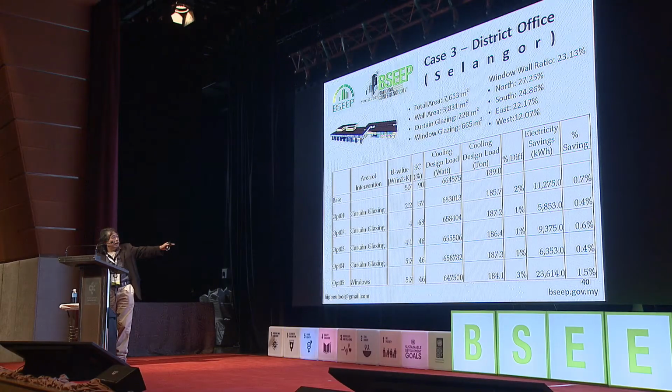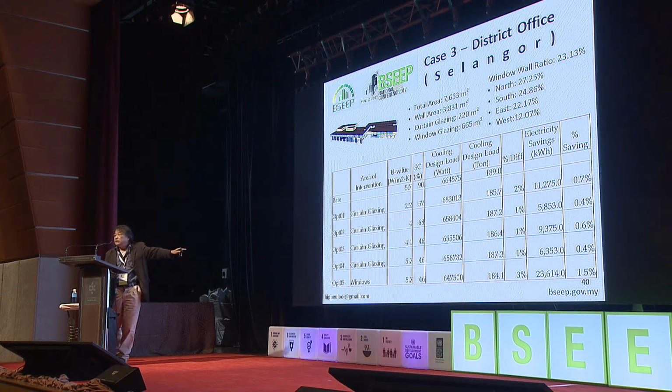So this is particularly interesting because we wanted to look at facade building envelope retrofitting. So we did a simulation, and this is the result. There are something like 800 to 900 square meters of glazing, and all these are single glaze. If I just do tinting, for example, SC 46%, but it's still a single glaze, then I can have so much energy saving.